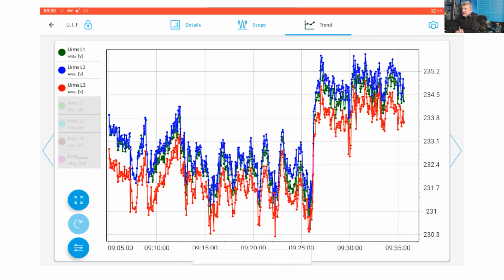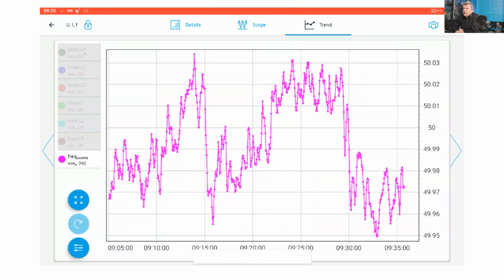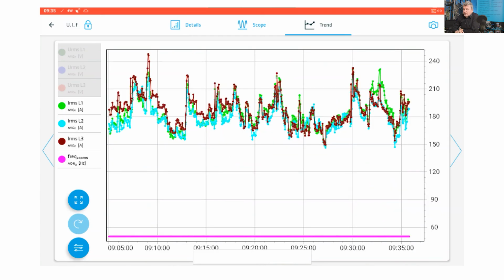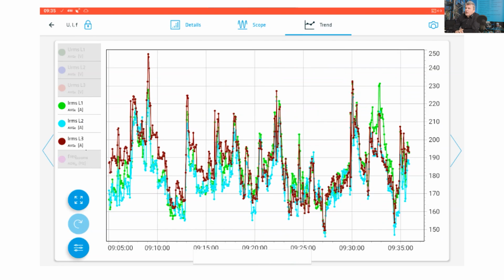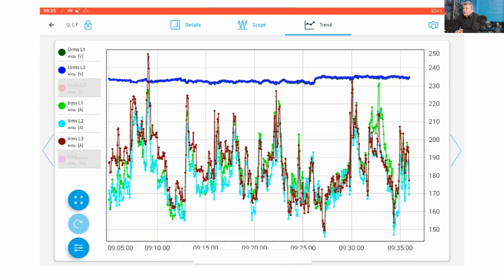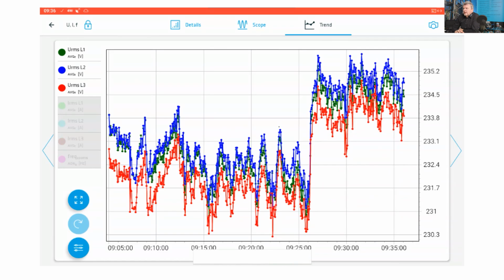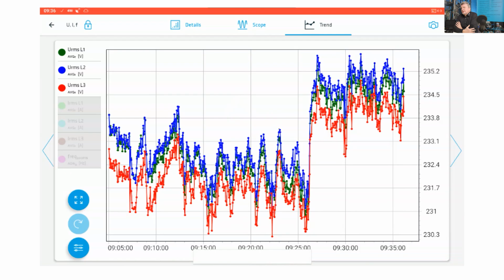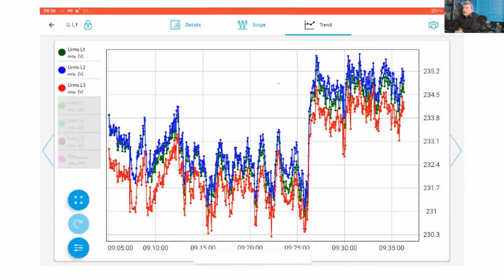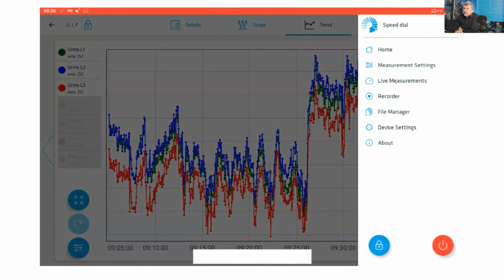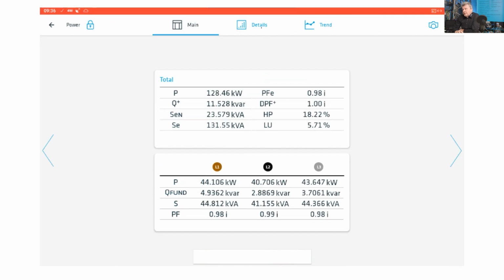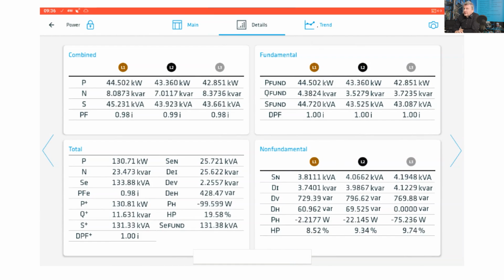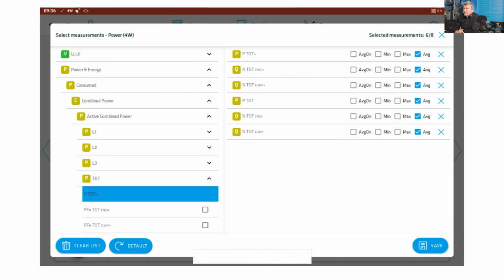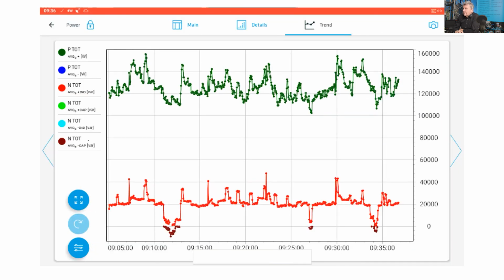For example, for better and more detailed analysis of the frequency, I have selected only the frequency view. Then, to select currents, I shadow the others which are not needed and monitor only the currents. The same for the voltages. This enables a faster and easier view of the selected events. And of course, you can make a screenshot if you need it. Practically, each view is selected in the same way. The main screen details, for example for power, combine fundamental and non-fundamental parts, and a total view of all interesting registers. And the same trend view with predefined selected measurements.